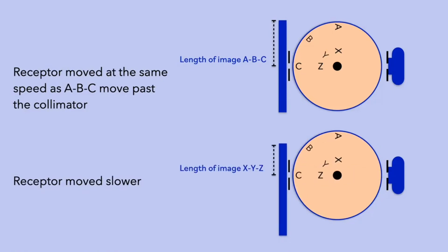Next, let's modulate the system and reduce the receptor speed. Note that the length of the registered image is shorter and in this case will more accurately represent the horizontal dimensions of structures X, Y, and Z. Images of structures A, B, and C are also recorded on this shorter length and thus are horizontally distorted and unsharp.